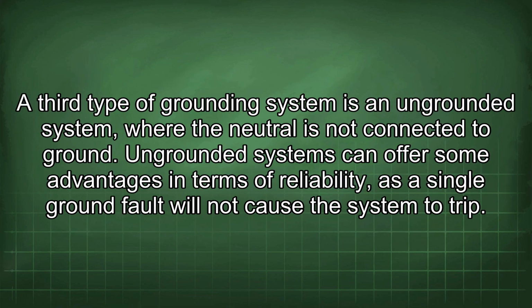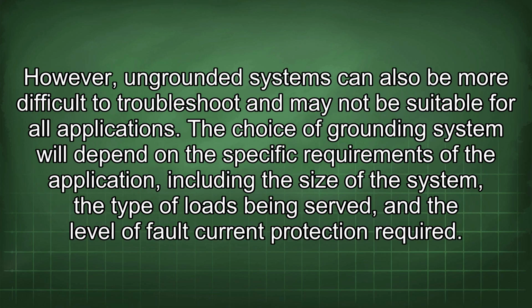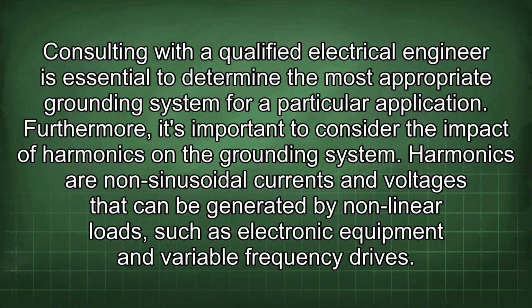A third type of grounding system is an ungrounded system, where the neutral is not connected to ground. Ungrounded systems can offer some advantages in terms of reliability, as a single ground fault will not cause the system to trip. However, ungrounded systems can also be more difficult to troubleshoot and may not be suitable for all applications. The choice of grounding system will depend on the specific requirements of the application, including the size of the system, the type of loads being served, and the level of fault current protection required. Consulting with a qualified electrical engineer is essential to determine the most appropriate grounding system for a particular application.